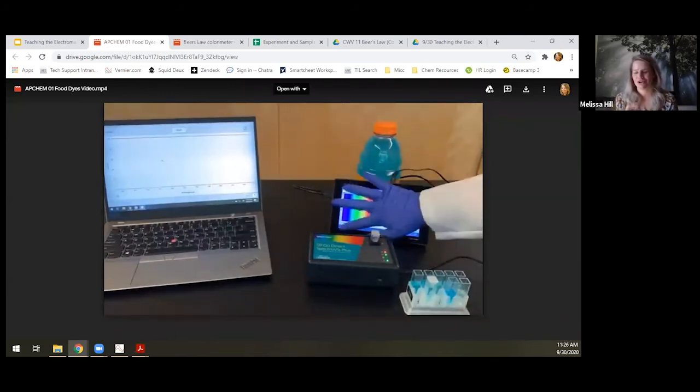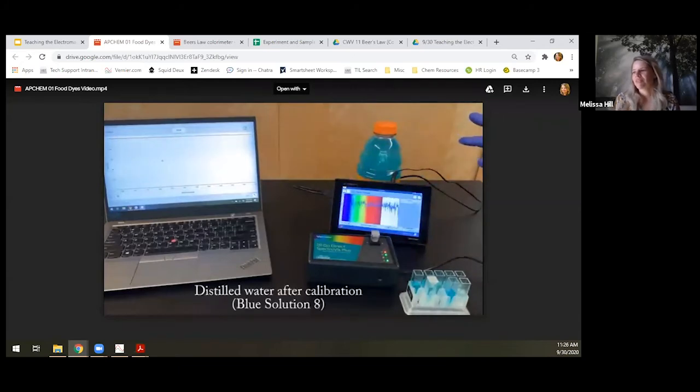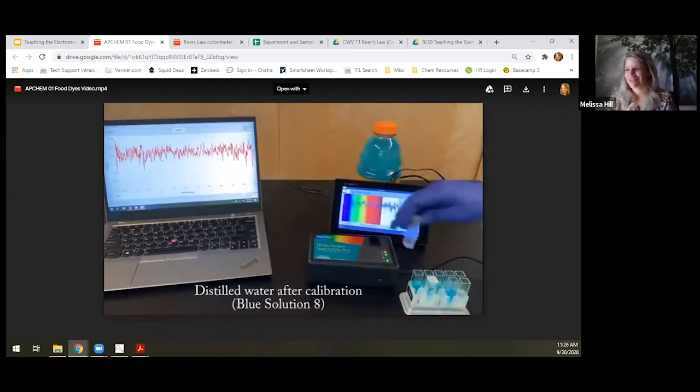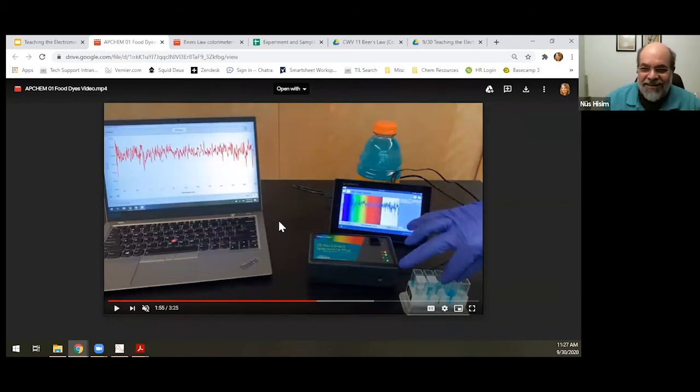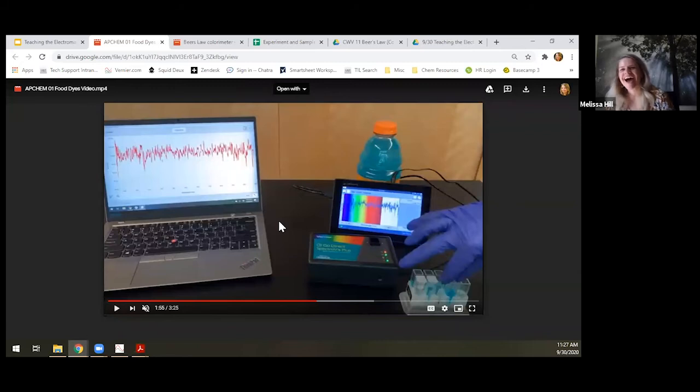So that's why I wanted to show it to you this way. But this is a great reason that troubleshooting instrumentation is helpful. I always like to do a warm fuzzy when I start my spectroscopy data and actually measure my distilled water and make sure it's a flat line. Well, that's not flat. Exactly, right? That's what your students would say.